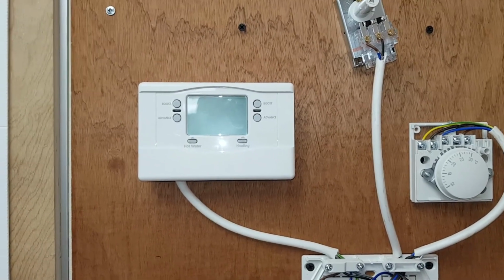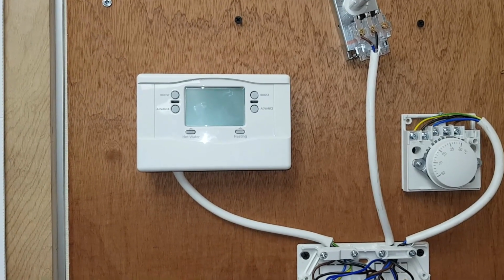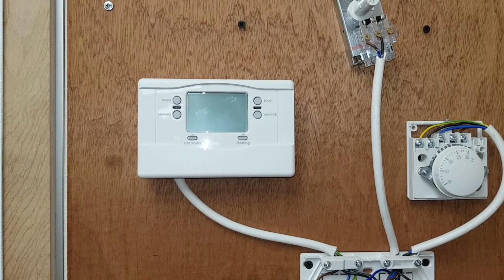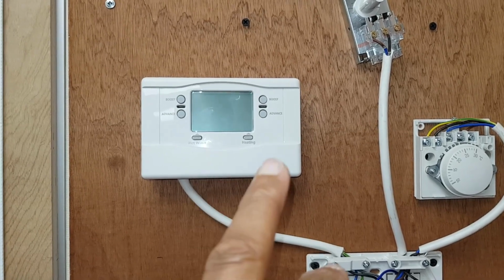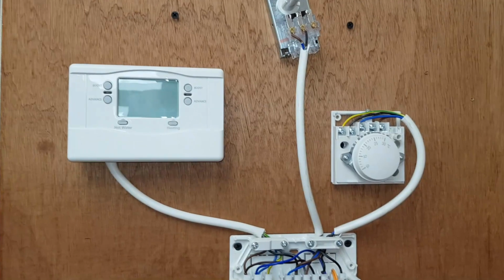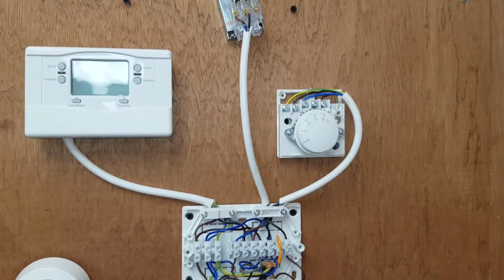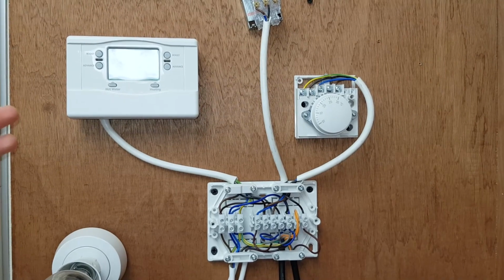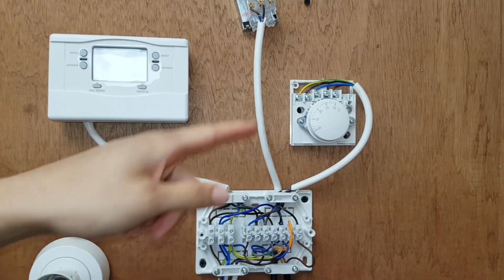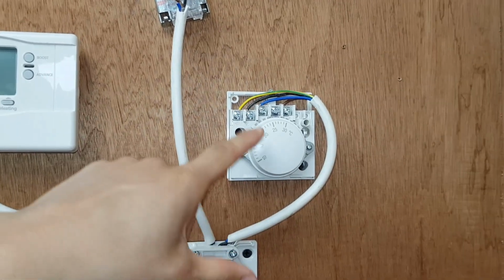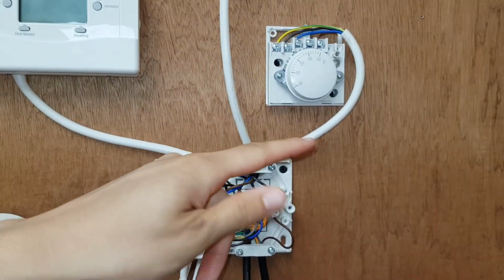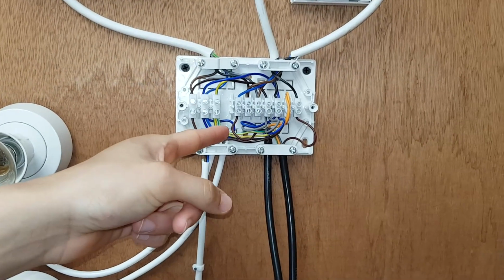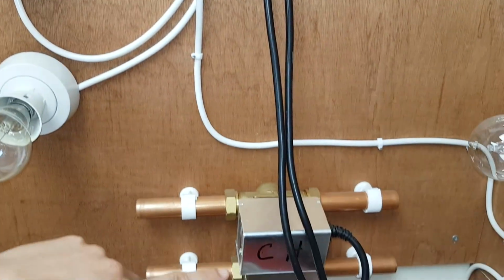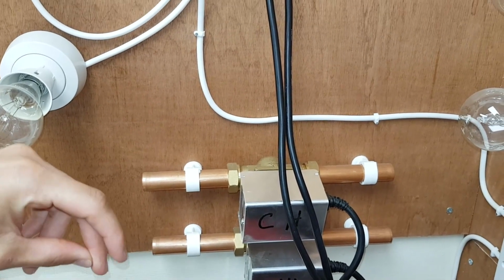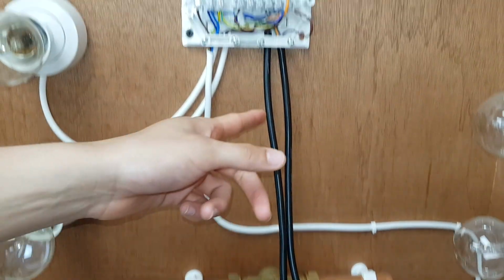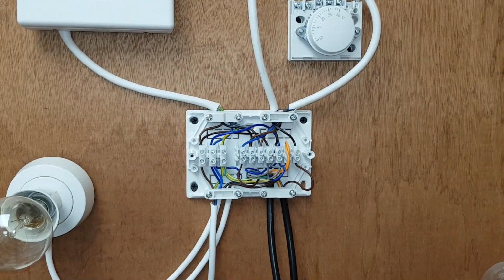Okay, Miles, now we're going to look at something else. We're going to look at the heating, and what I want you to do now is tell us that from 4, where does it go around this S-plan system? Just explain that for me, please. Okay, so from the central heating terminal 4, we go to the room thermostat, terminal 1, which makes a switch to terminal 3, which then comes down to your brown wire here, which activates the motor inside the zone valve. Then a micro switch is made, which goes to the orange wire, starting the pump and boiler.